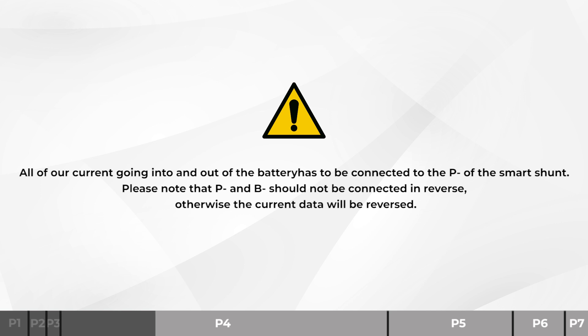All of our current going into and out of the battery has to be connected to the P negative of the shunt. Please note that the P negative and B negative should not be connected in reverse. Otherwise, the current data will be reversed.